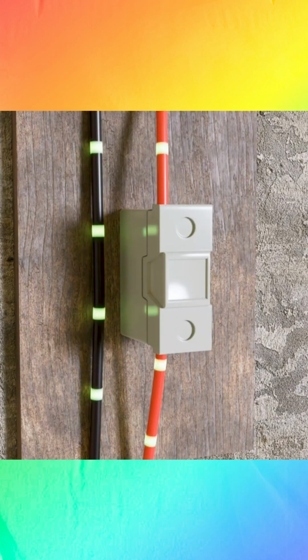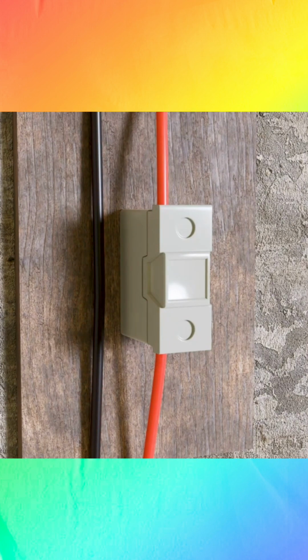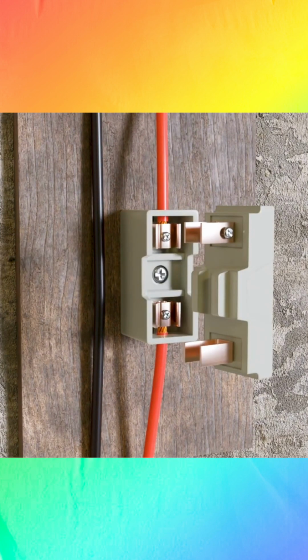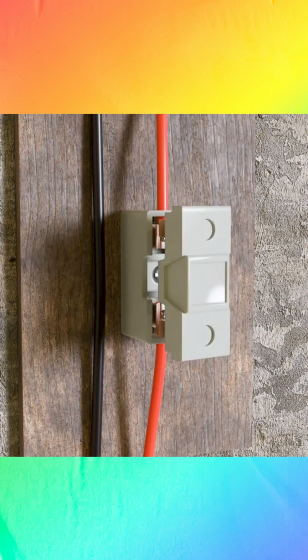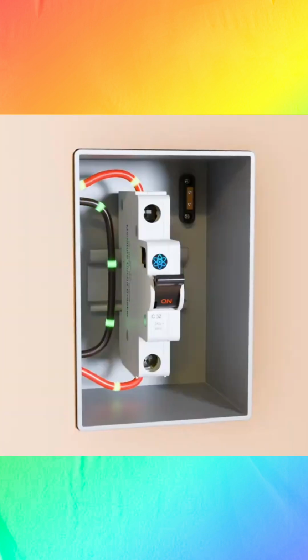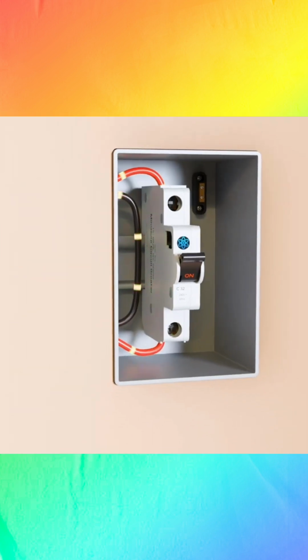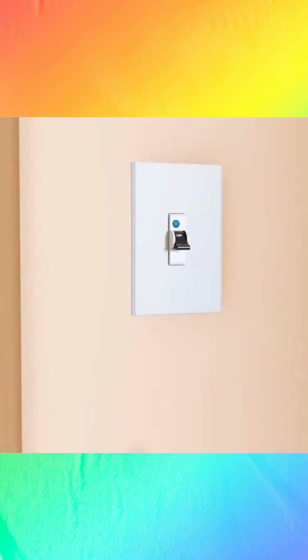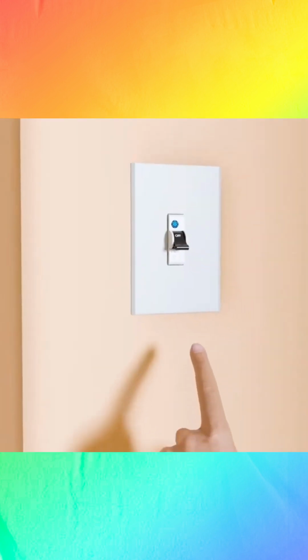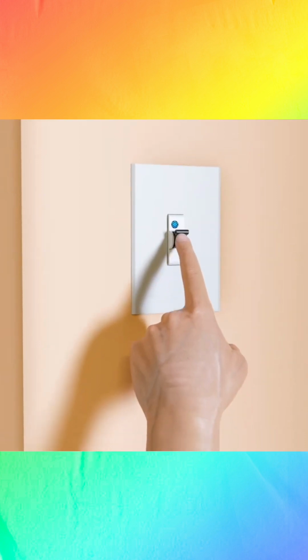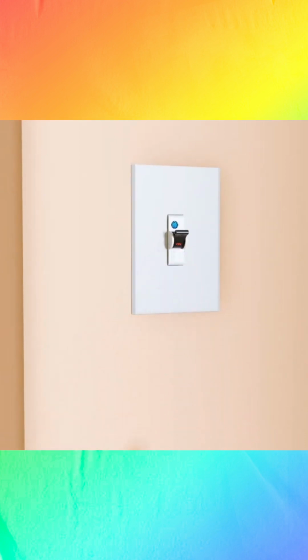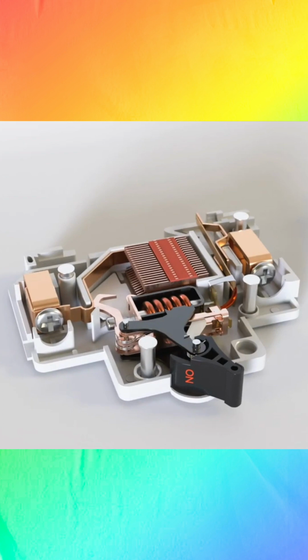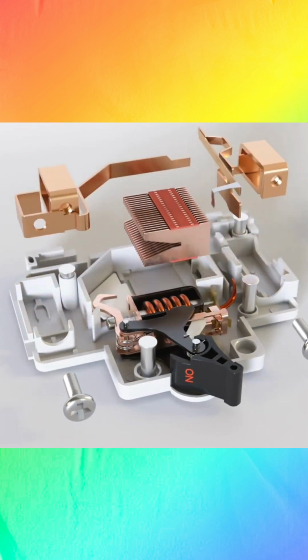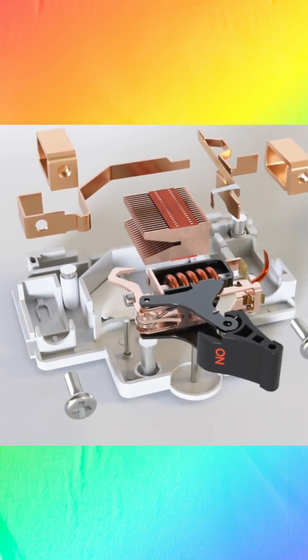The main downside of using a fuse is that, whenever the fuse wire melts, we have to manually replace it with a new one. But in case of an MCB, no such problem is faced. When an MCB trips due to a fault, we can easily switch it back on after fixing the problem. Unlike a fuse, we don't need to replace anything. Let's explore how a miniature circuit breaker detects short circuits and overloads by understanding its internal working.